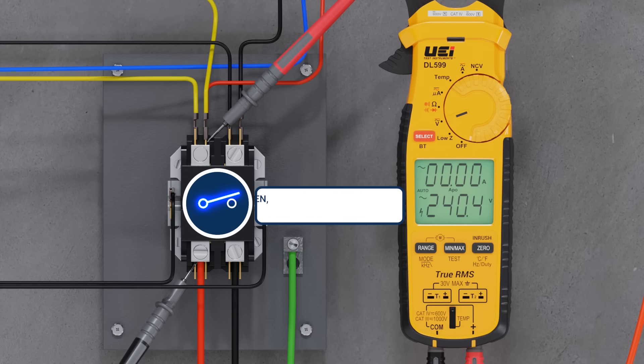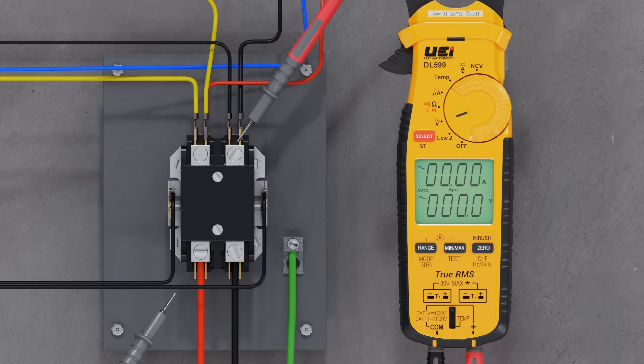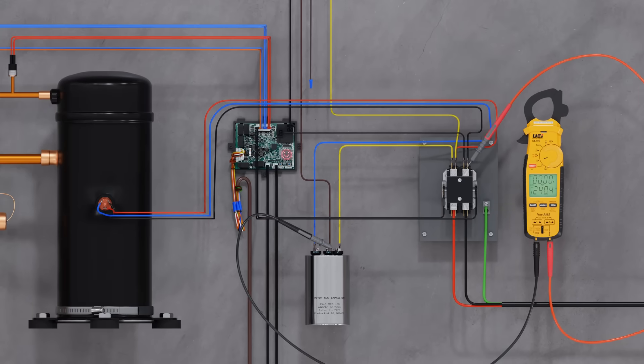When the switch is open, that's when you may see voltage across it. This is why, generally speaking, you'll put one lead on the opposite side of the circuit — either neutral, the other side of 240 volt or three phase power, or in some cases to ground — and you will walk through the circuit with your other high voltage lead, measuring that pressure drop or voltage difference as you go through the circuit.